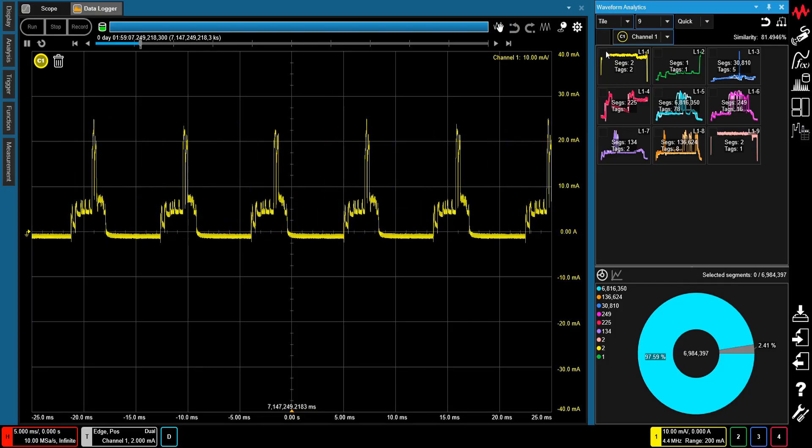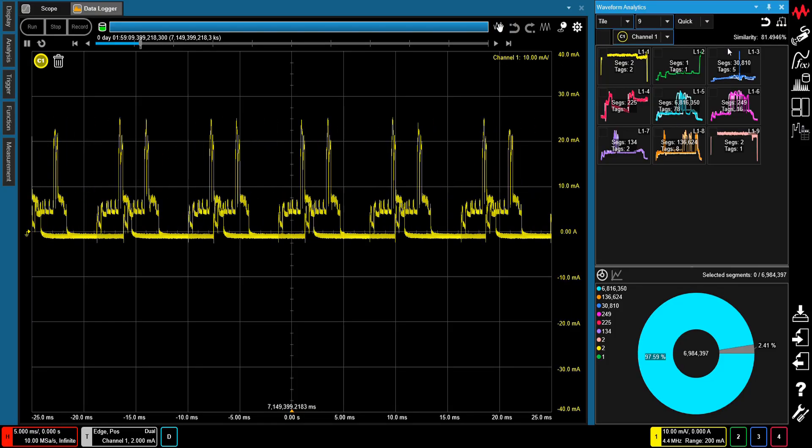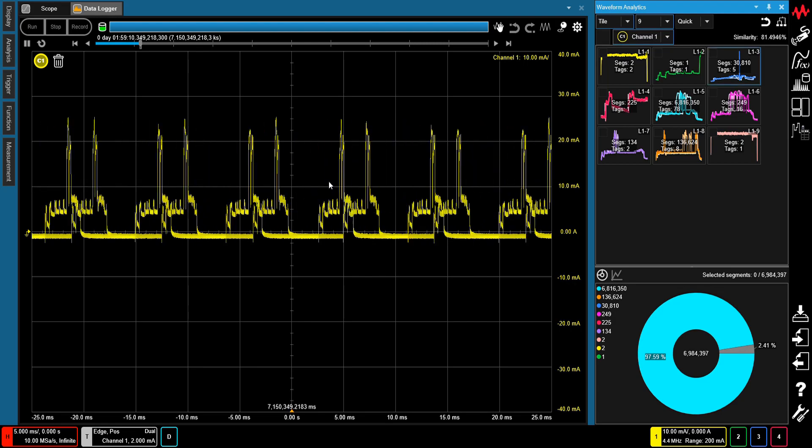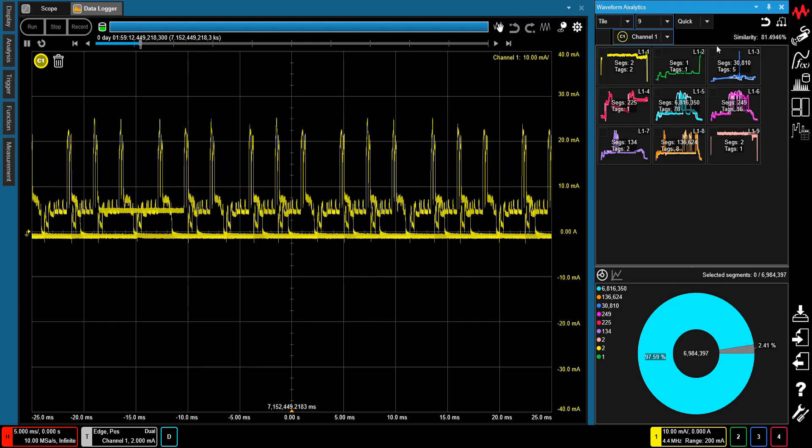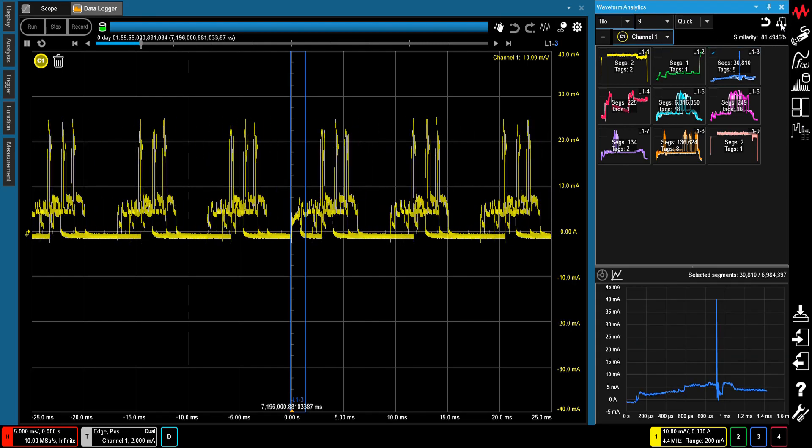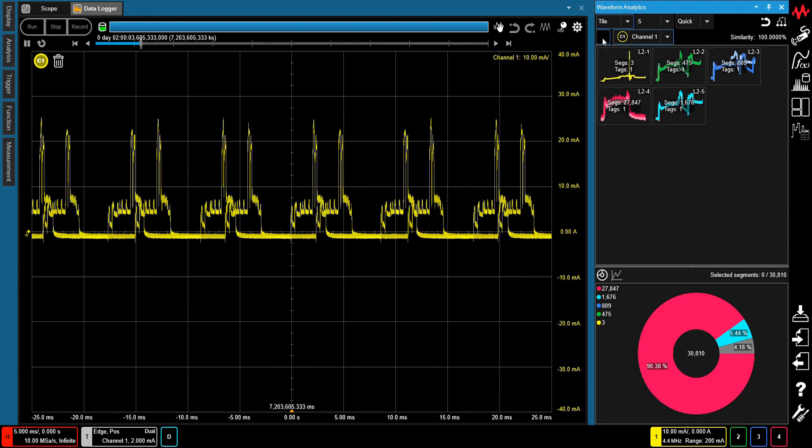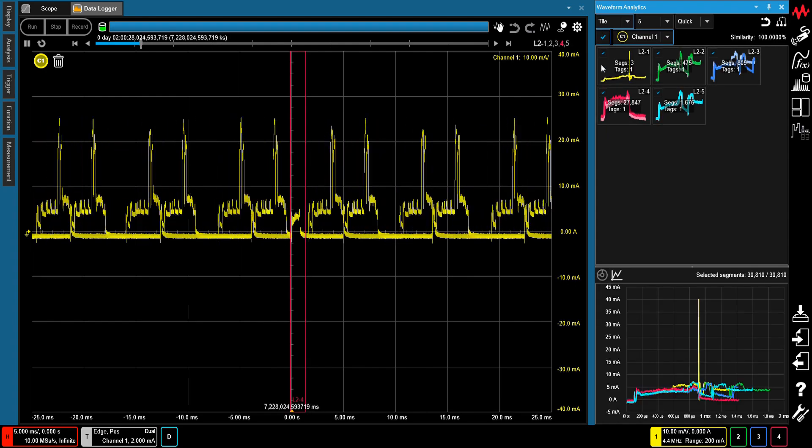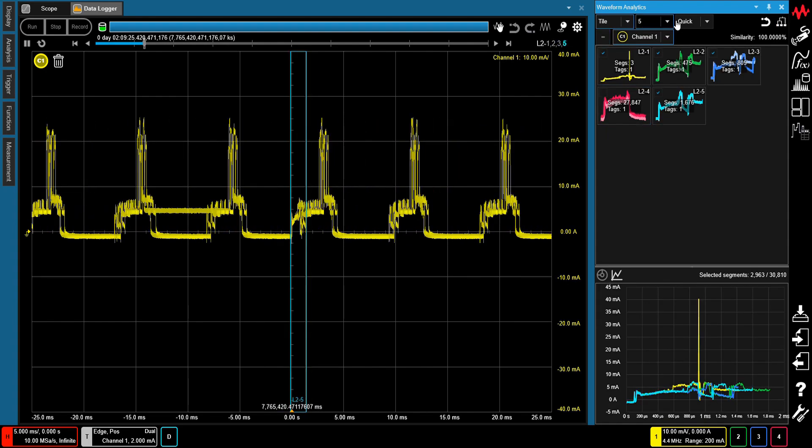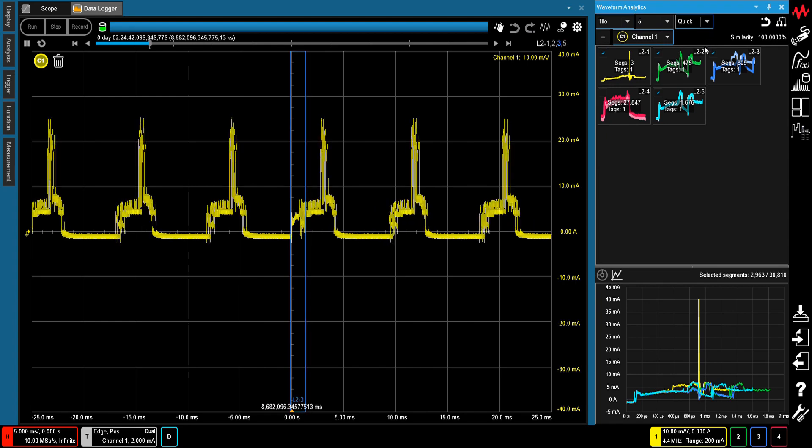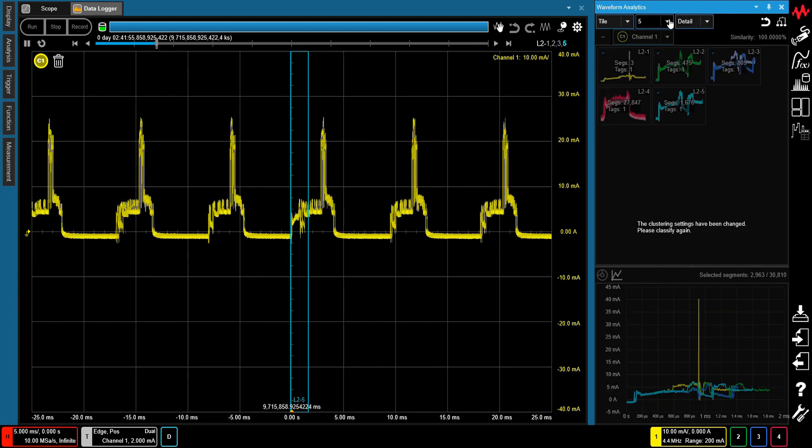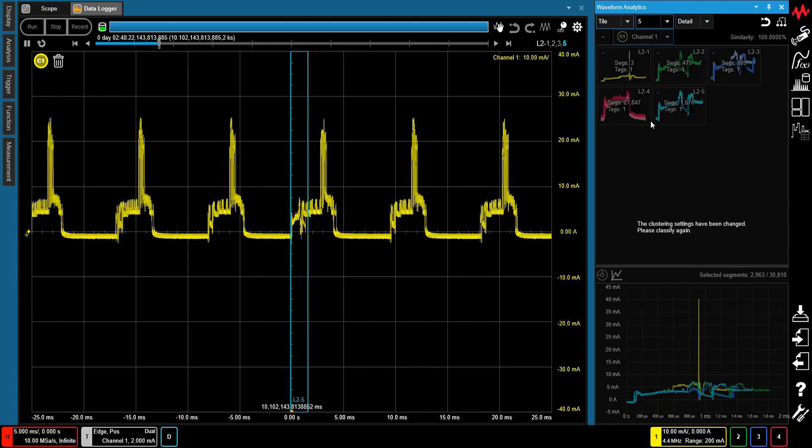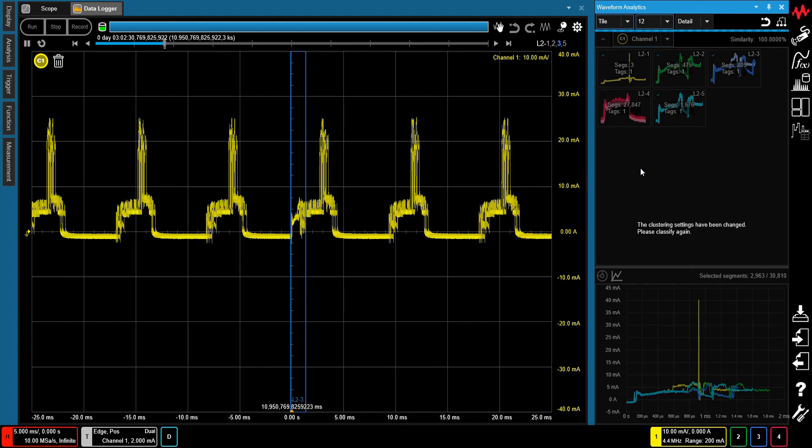This allows you to view classified waveform information immediately after the measurement is complete without the need to wait for any post-processing analysis. You can also select particular waveform clusters and parse them into sub-clusters for further examination, and this process can be repeated multiple times to identify more subtle waveform differences.